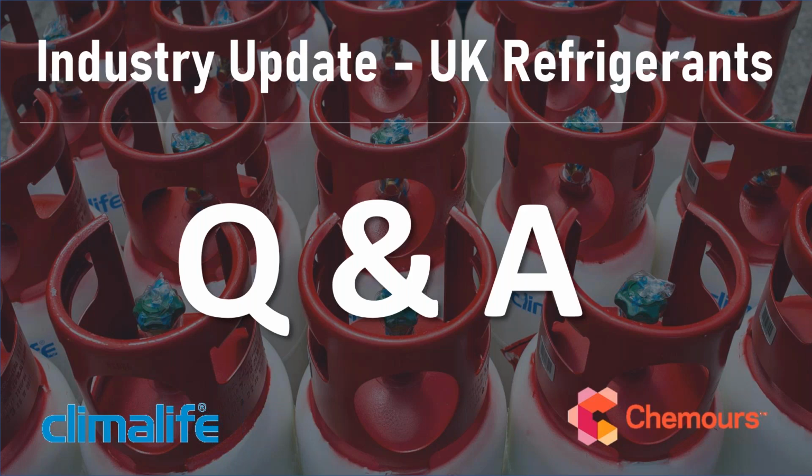Yeah, I think we're talking about low temperature applications, and you're saying not A2L. I think that's a bit pie in the sky now. I mean, there are products around, but they tend to have higher GWP. If you want something that's less than 600, you're talking about using an A2L really, or you're talking about going to something like ammonia if that's available to be used.